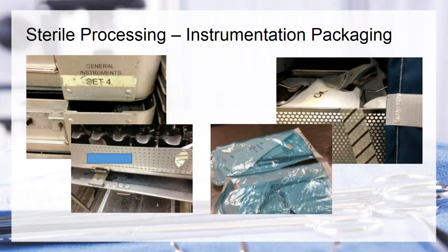The reason we can't do that anymore is you create air pockets. And what Amy had found out was that if steam cannot penetrate those air pockets, then the item cannot be considered sterile. So just like when you do your Bowie-Dick test, you have to make sure that you have that dynamic air removal. This is the same concept.